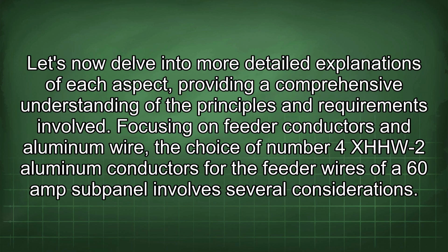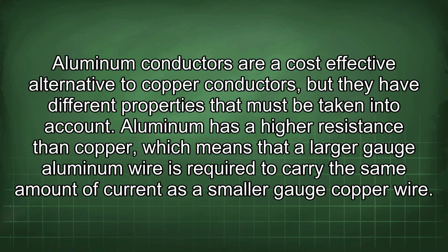job. Let's now delve into more detailed explanations of each aspect, providing a comprehensive understanding of the principles and requirements involved. Focusing on feeder conductors and aluminum wire, the choice of number 4 XHHW-2 aluminum conductors for the feeder wires of a 60 amp subpanel involves several considerations. Aluminum conductors are a cost-effective alternative to copper conductors, but they have different properties that must be taken into account. Aluminum has a higher resistance than copper, which means that a larger gauge aluminum wire is required to carry the same amount of current as a smaller gauge copper wire.